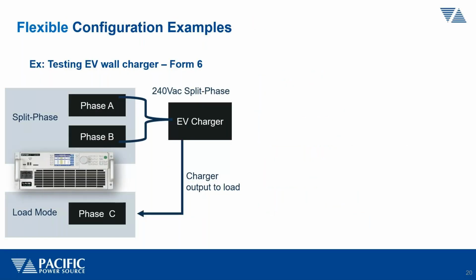Let's look at a couple of examples of how you would deploy that kind of flexibility. For example, in this case, you're testing, let's say, a split phase level 2 EV charger, a home charger, and you're using 2 phases to connect the 240 volt split phase at the input, and then you use one of the other phases that's left, in this case with a load mode capability option, as a load to load down the charger output.